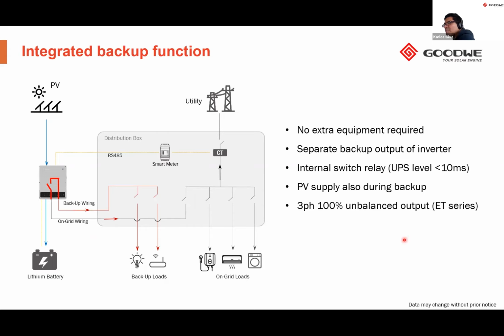So in a backup situation, the backup output is 100% unbalanced. So that means each phase will regulate its power in accordance to the power draw of the backup load. So that means that in theory, for example, the backup output could be producing 3 kilowatts on one phase, 1 kilowatt on phase 2, and 1.5 kilowatts or 2 kilowatts on phase 3. So that unbalanced output also does apply to the on-grid output as well.